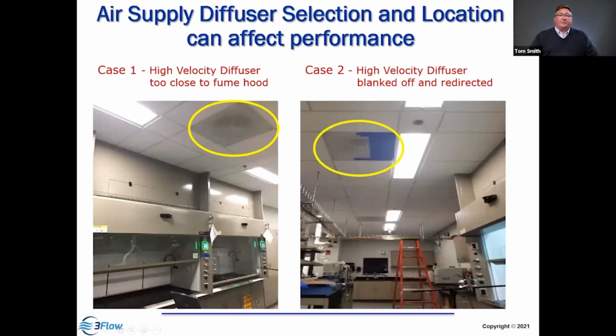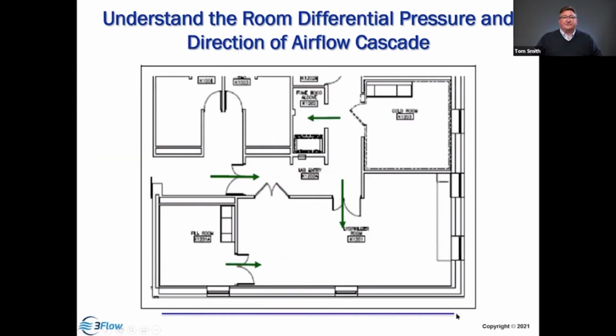In this example, and we're going to show the results of this over the next day and a half, we're looking at a supply diffuser. It's too close to the hood. It's only 3 feet away. It's got an airflow velocity that's directly impacting the plane of the sash. And then we had to blank it off. We had to put tape over it to see if we could improve the performance of the hood by creating a different airflow pattern. And I'll show you the results as we move forward through the different test discussions.